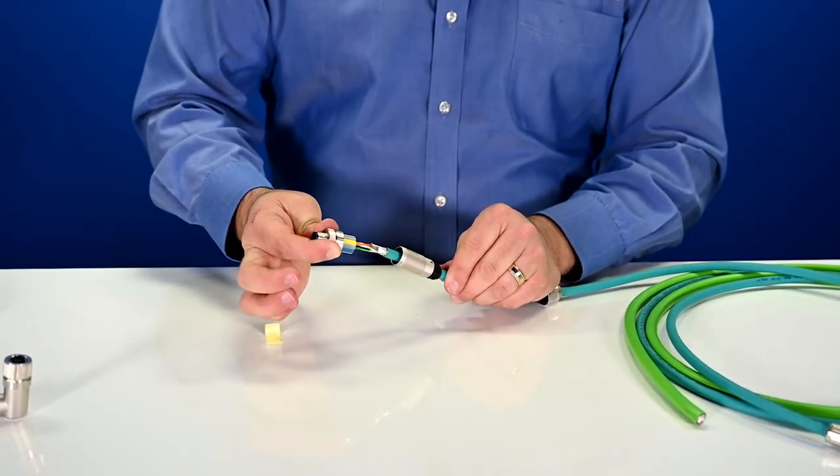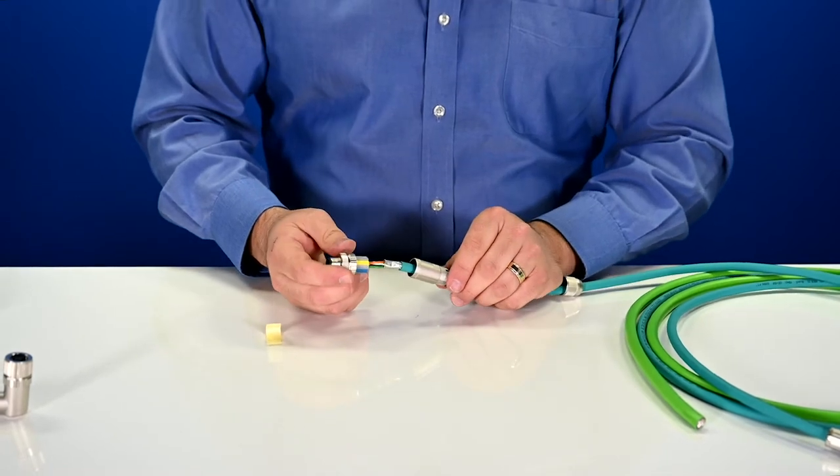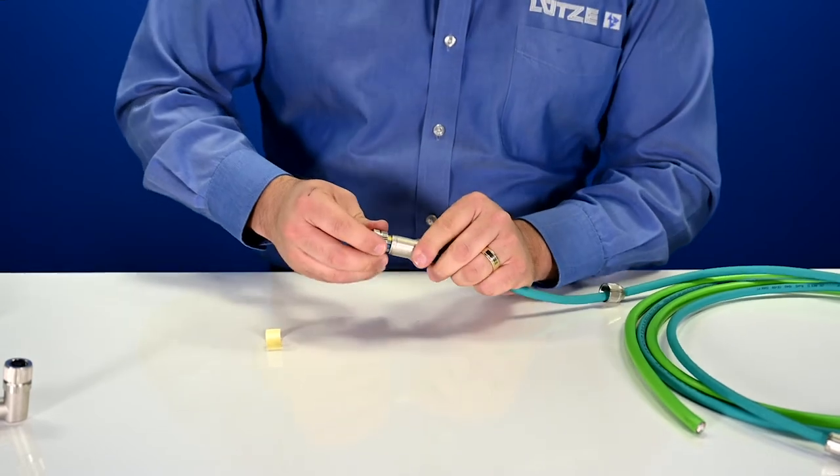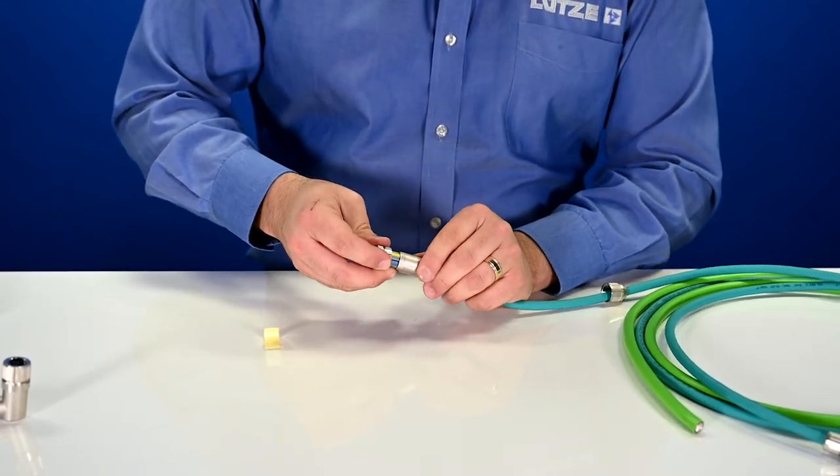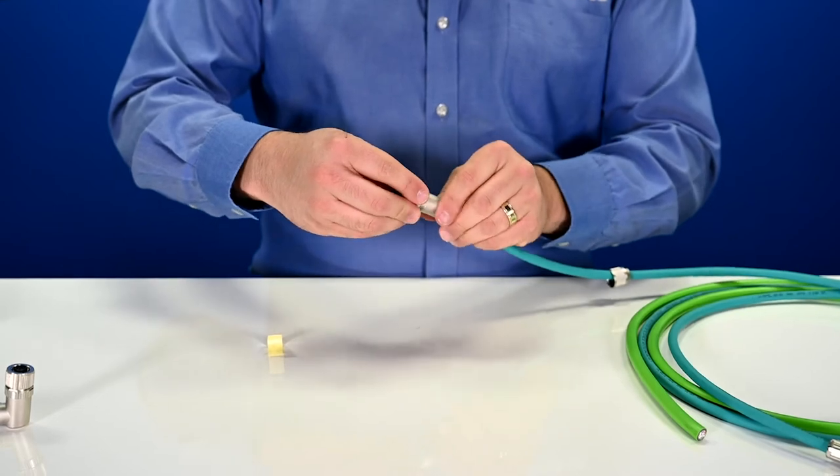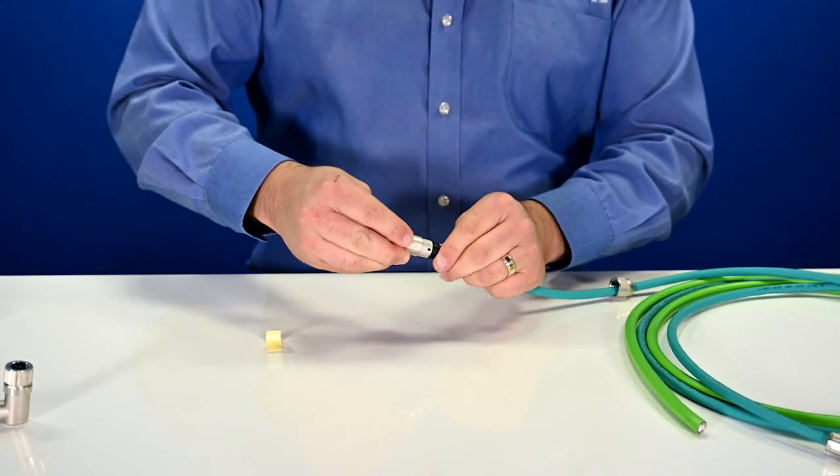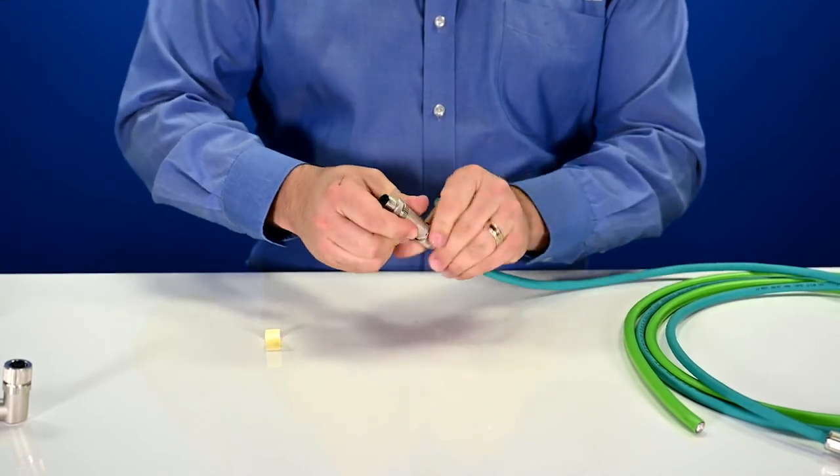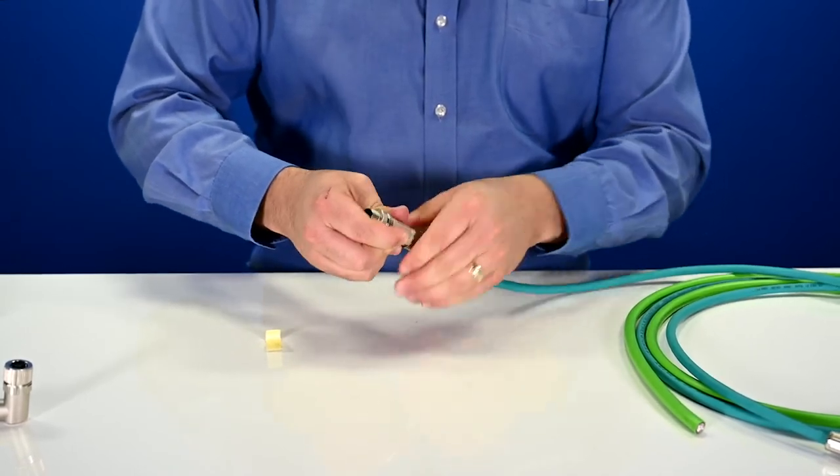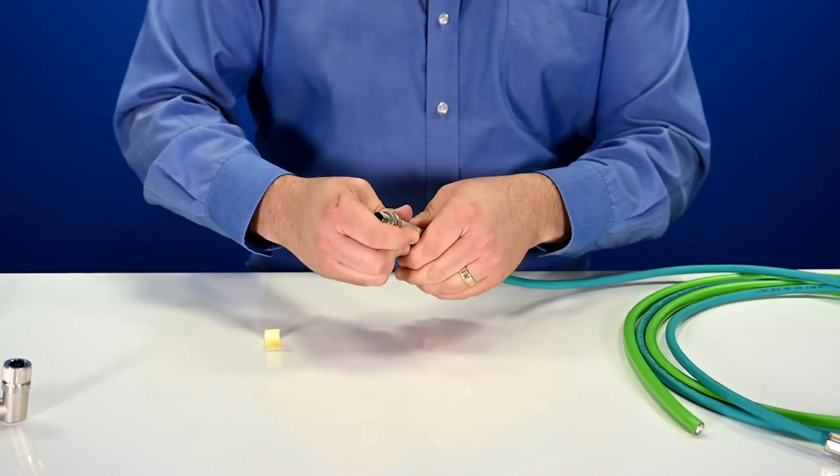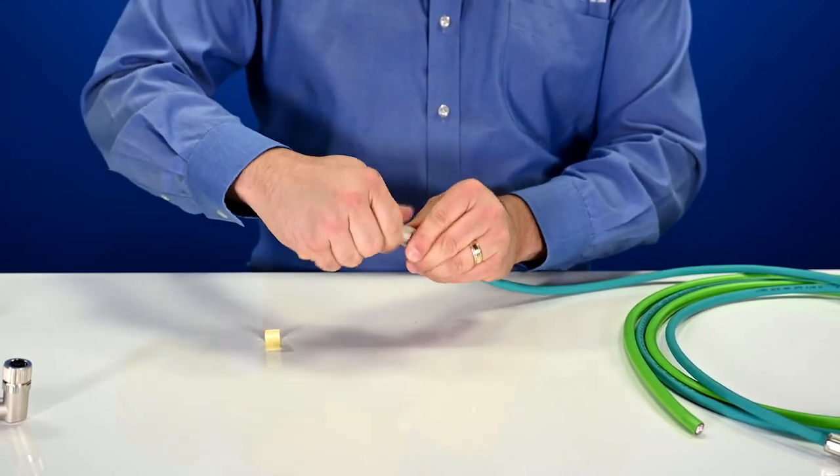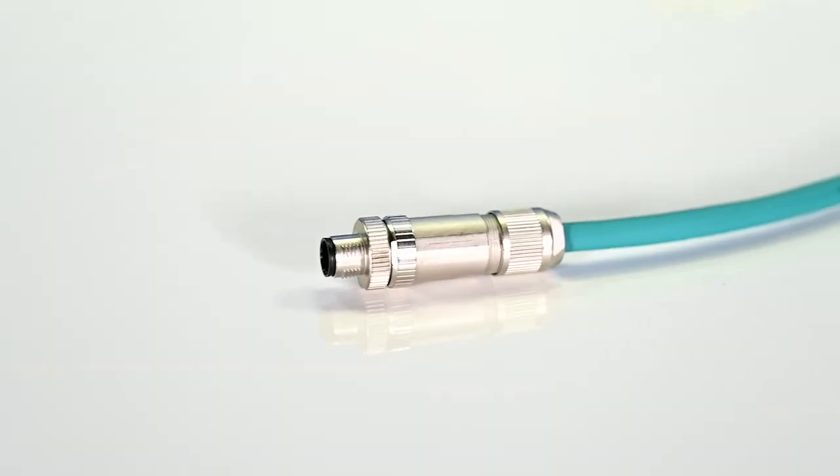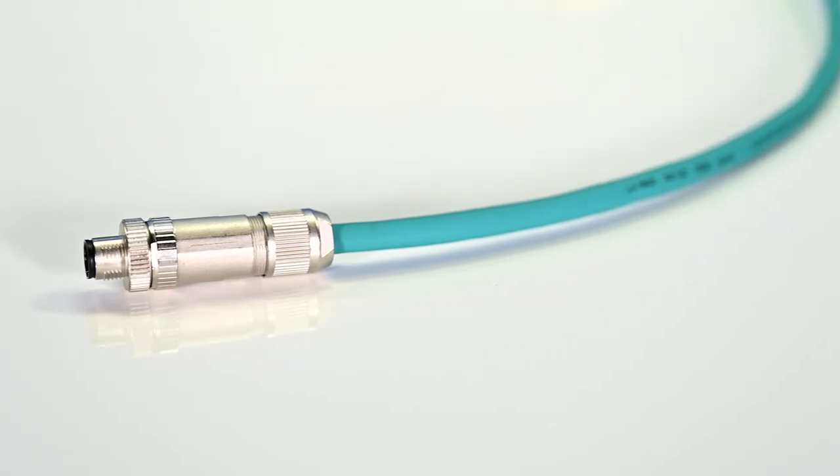Now that we have all of our conductors terminated, all we have to do is close up the housing. Simply slide the housing up over the connector. Make sure to rotate it so that it's aligned with the keyway, and it'll slide right on. Close that connector up and tighten down with the integrated strain relief. And now you have an M12 connector that's ready to terminate in the field.